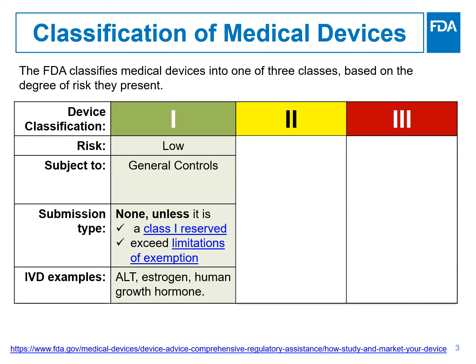This means that the companies will validate the device and will keep the documentation on file without submitting to FDA. That is unless the assay is considered a Class 1 reserved device or if any of the limitations of the exemptions is met. For example, ALT and the human growth hormone test systems do not need a 510K unless they are intended for point-of-care use, which is a limitation of the exemption.